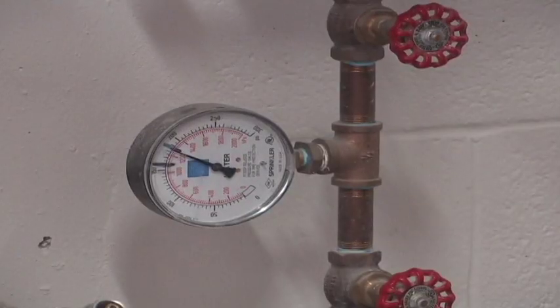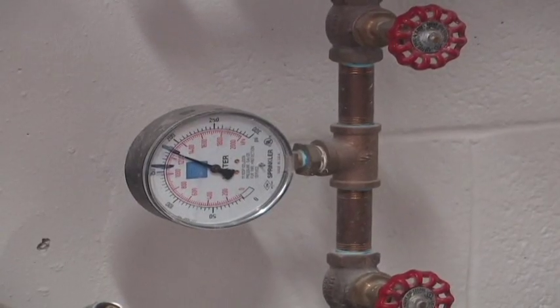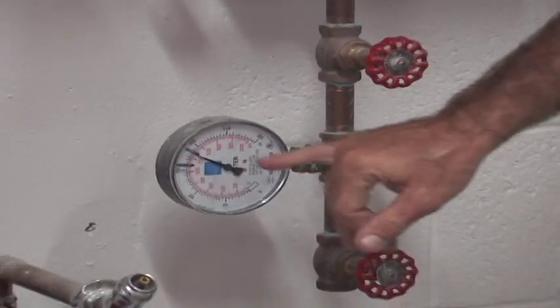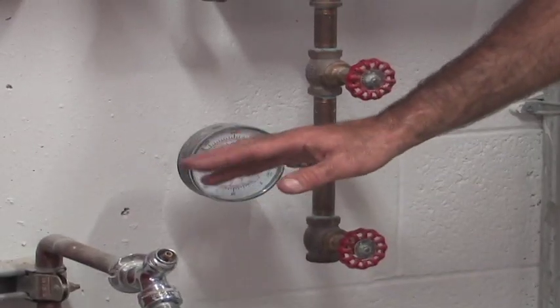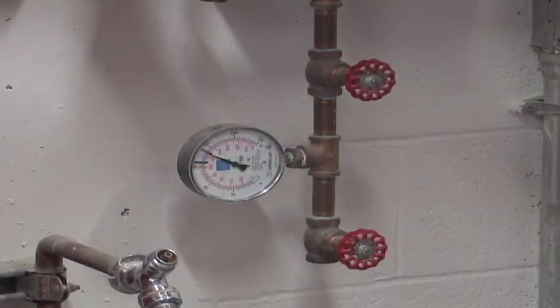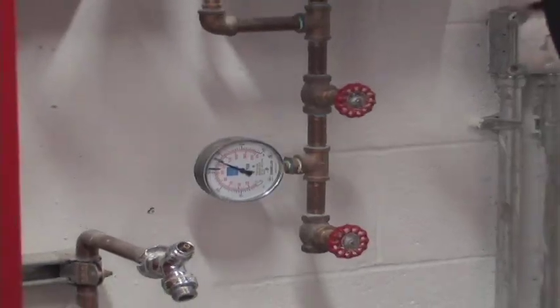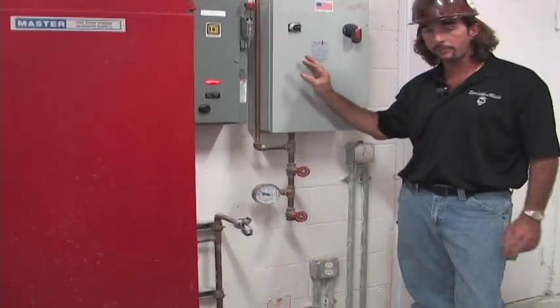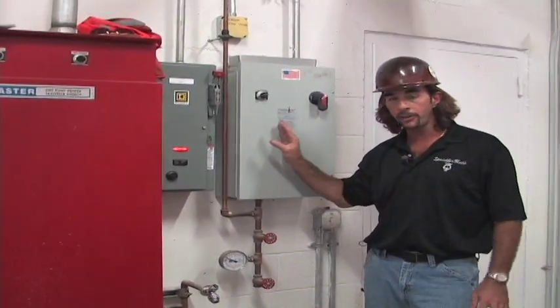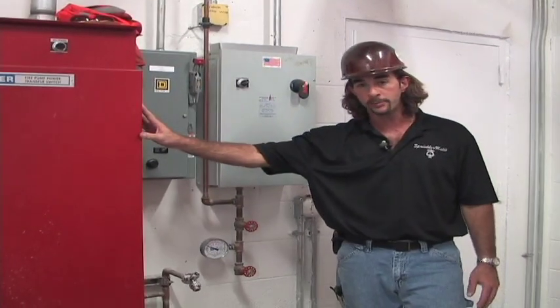Our fire pump over here, when we get to it, starts at 150 psi. This jockey pump should cycle weekly, daily, however it does, so that the main fire pump does not turn on. That's the only sole purpose of the jockey pump. It doesn't put out a fire. The only thing it does is stop the fire pump from turning on.